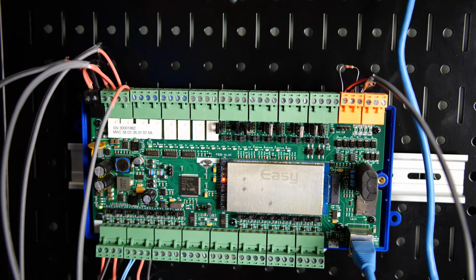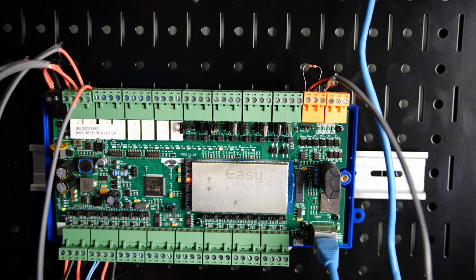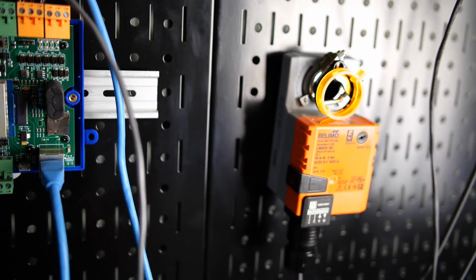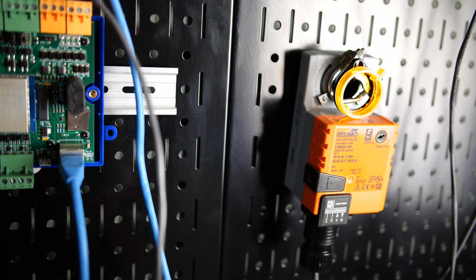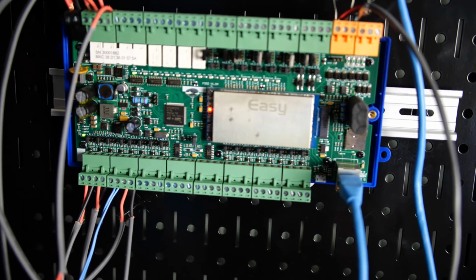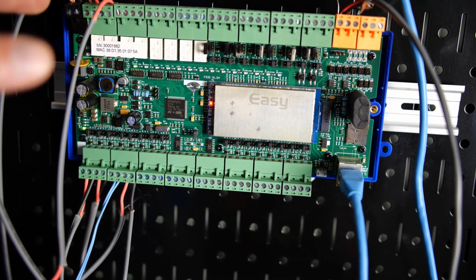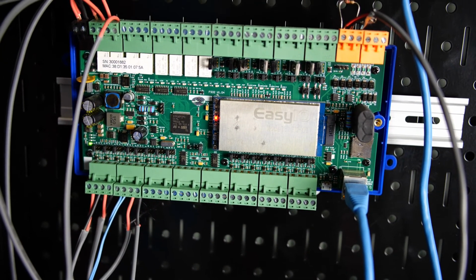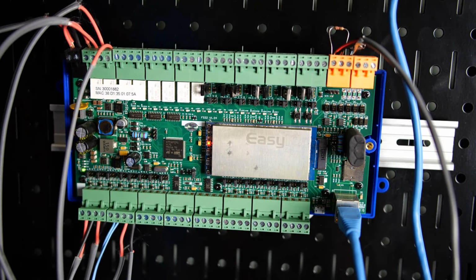So when we talk about a shared common, we talk about how this actuator over here is using the same hot and common, the same circuit as this transformer that the controller is using. So if that's the case, then we can actually just hop the common over from one of the outputs. We can hop the common over and just wire it directly into the terminal block because it's a shared common. Now, that's not what I recommend.